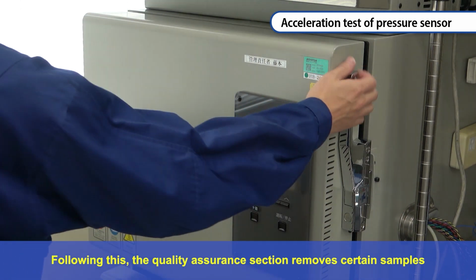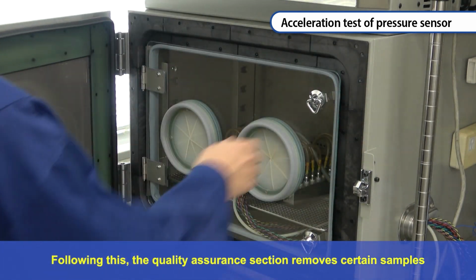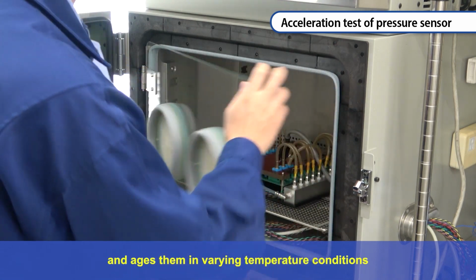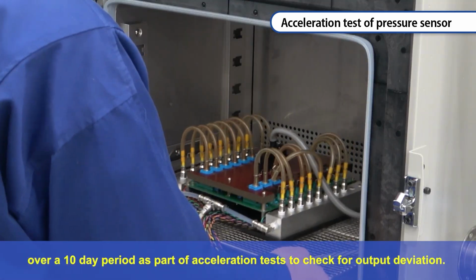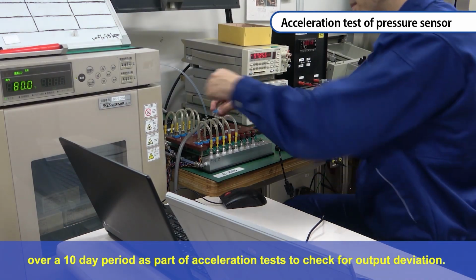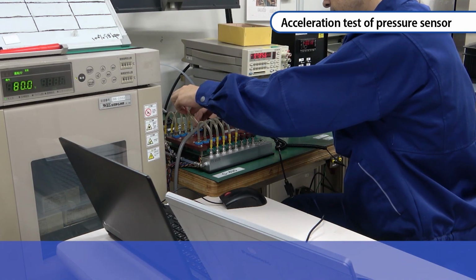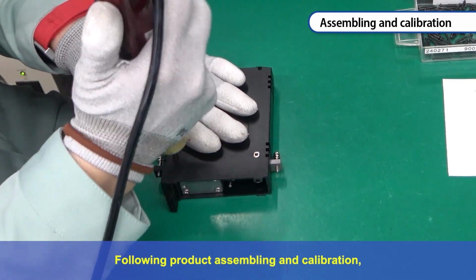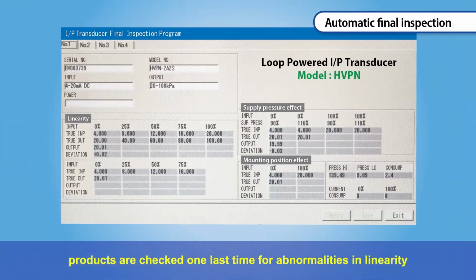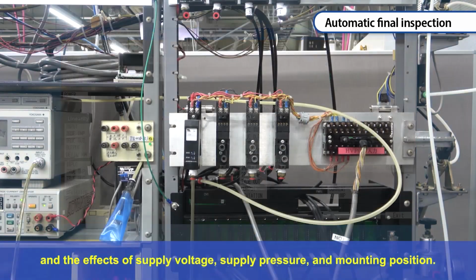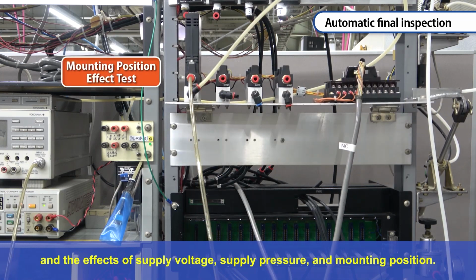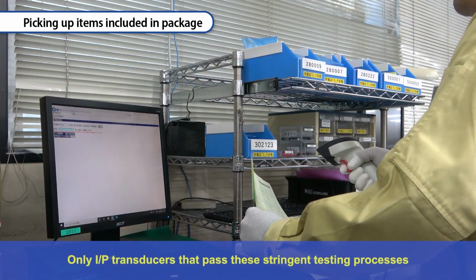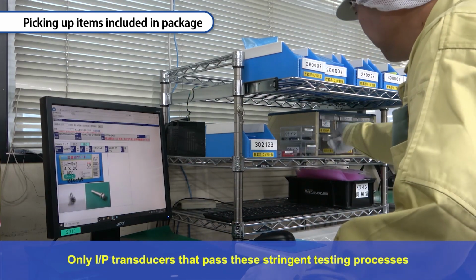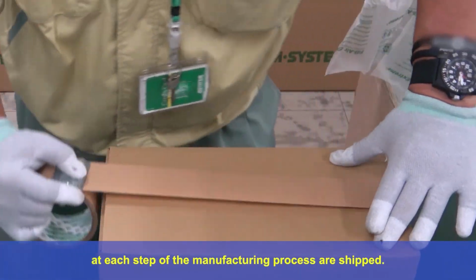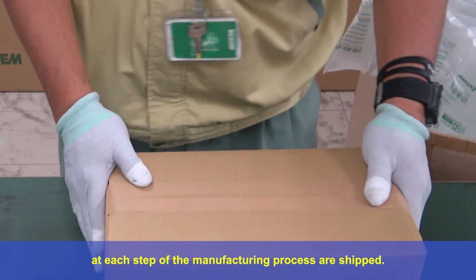Following this, the quality assurance section removes certain samples and ages them in varying temperature conditions over a 10-day period as part of acceleration tests to check for output deviation. Following product assembling and calibration, products are checked one last time for abnormalities in linearity and the effects of supply voltage, supply pressure, and mounting position. Only I-to-P transducers that pass these stringent testing processes at each step of the manufacturing process are shipped.